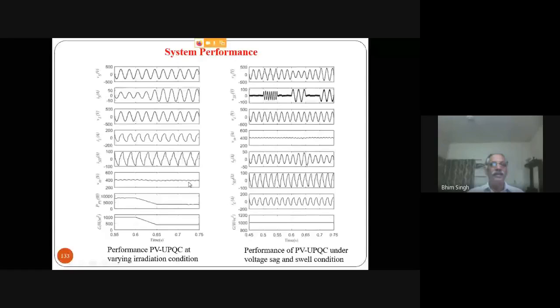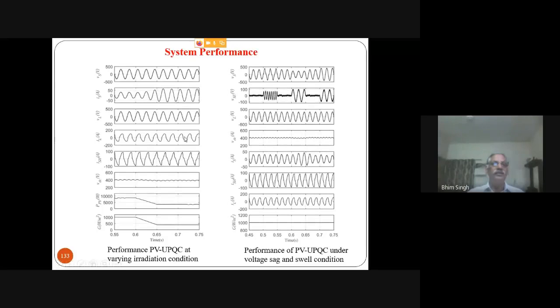After feeding the load, it goes to the grid. You can see the current is typically out of phase. This is the load voltage, load current, and shunt compensator current, generating harmonics as well as reactive power, typically for the load compensation, as well as active power it is feeding. When you have a voltage swell or voltage distortion, it takes care by injecting the voltage, and the load voltage is balanced and completely sinusoidal and regulated.